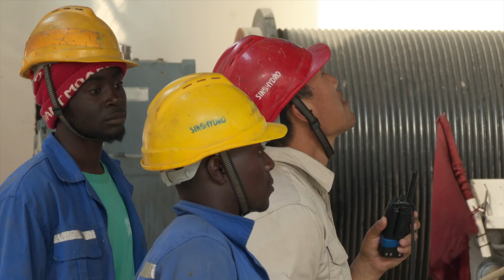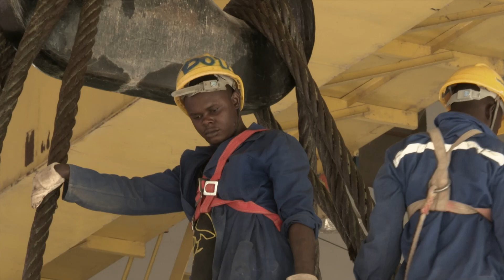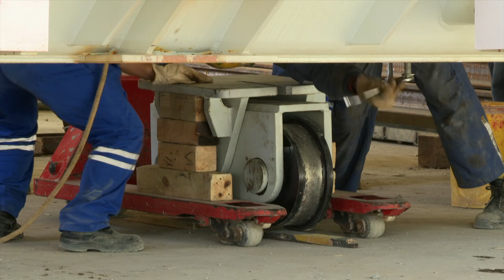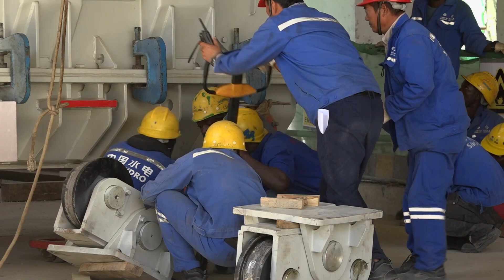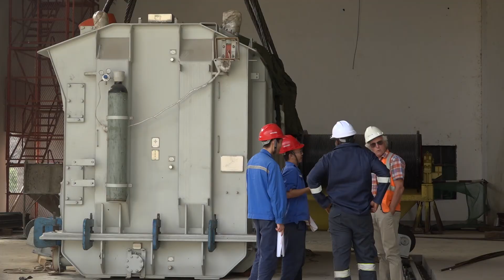They are rated 13.8 to 330 kV and 187 MVA. We are now unloading the transformers, bringing them to their respective transformer cells, what we call transformer cells. This is a cell for transformer number 5, or generator transformer number 5, coming from generator number 5.